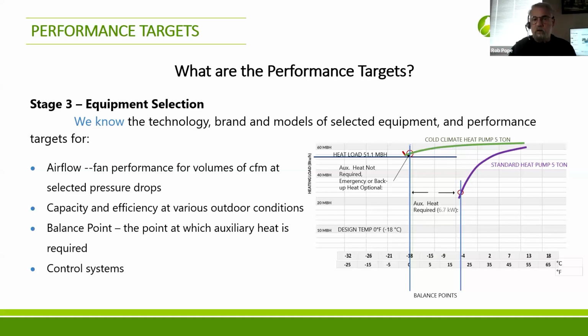And this is a separate entity in the process because there's a lot to the equipment selection because it's based on the load calculations, and you've got to look up the fan curves, performance curves, and all that stuff. And you've got to do a balance point calculation, and that's what you see on the right there, an example of a balance point calculation. So that's part of the process and establishes some of the performance targets that we'll be checking down the road.